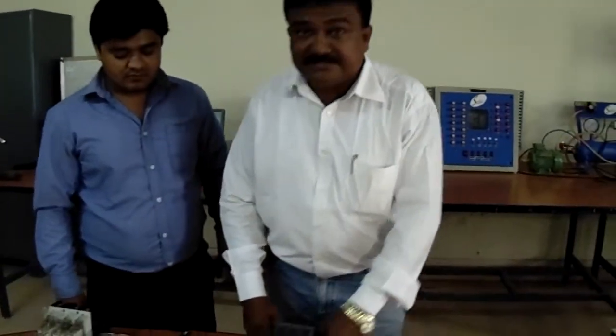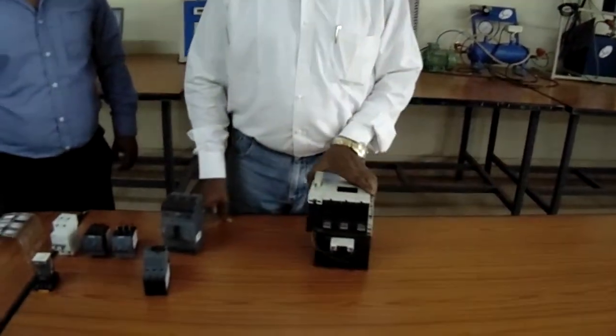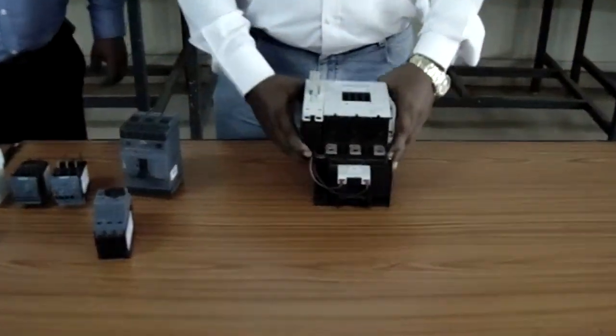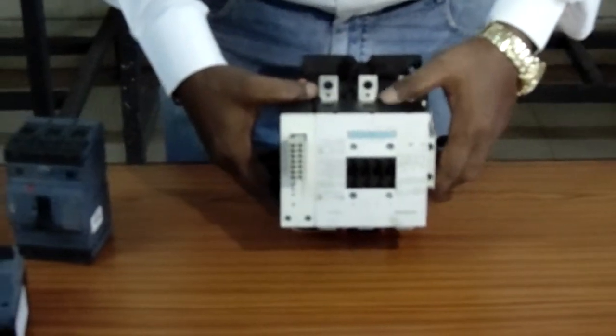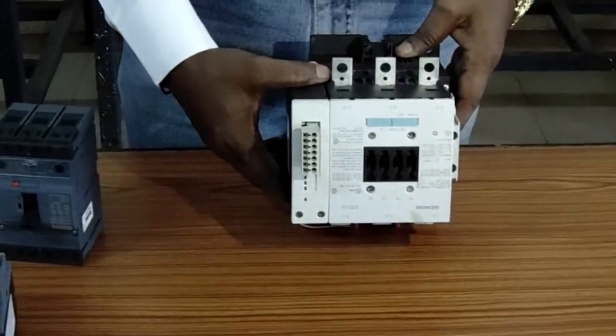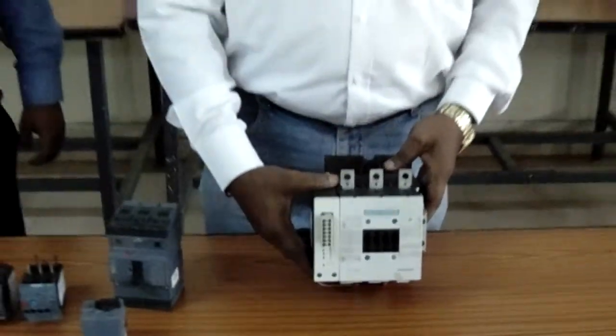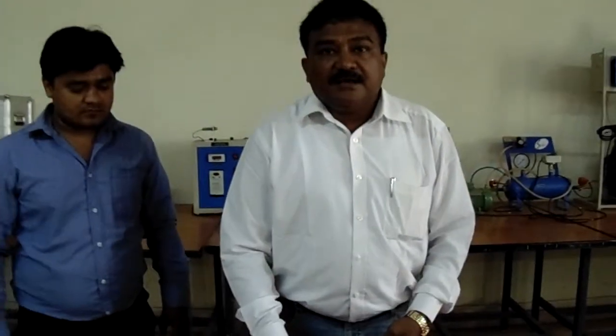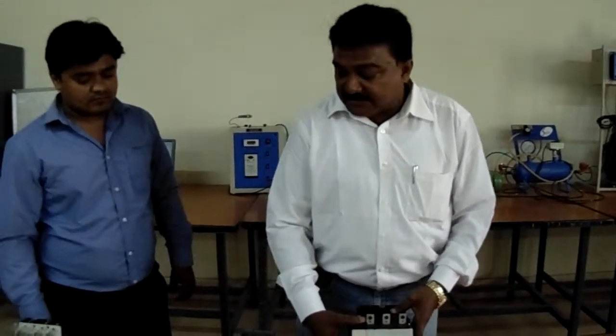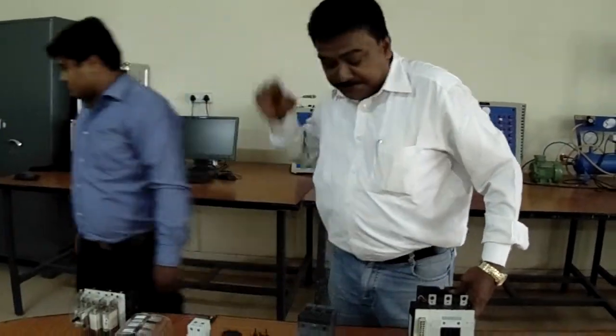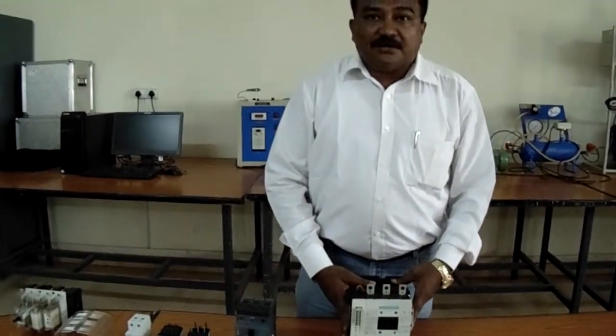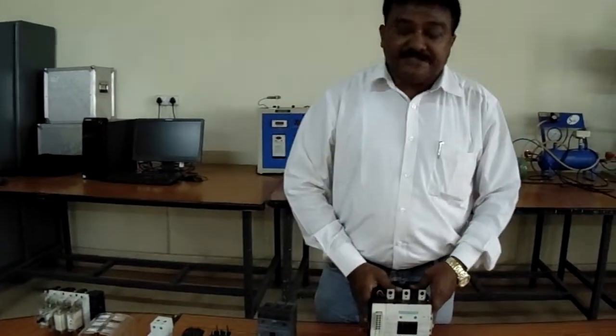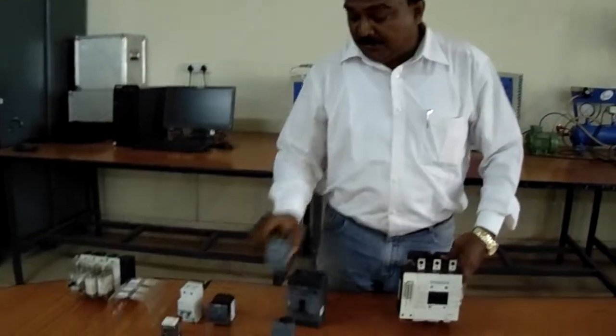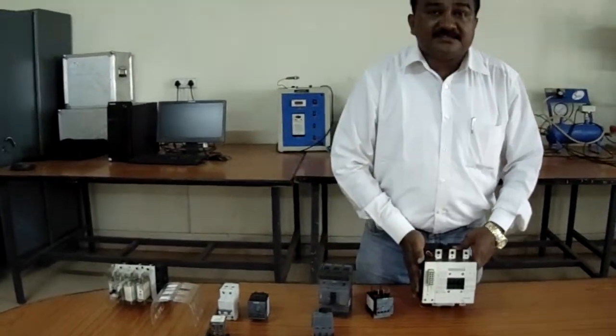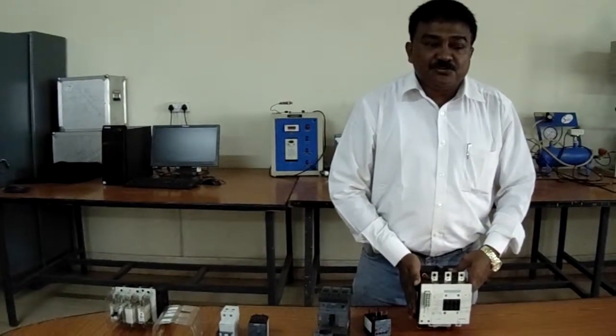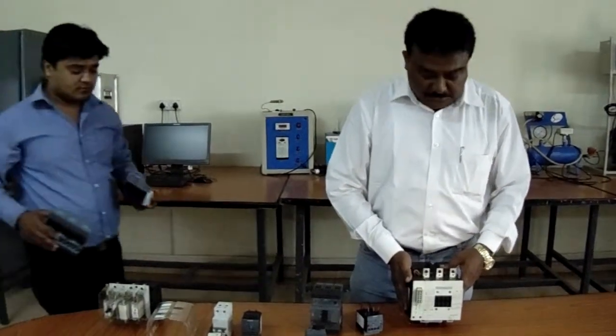Now coming to the starters of a 3-phase induction motor. Basically, conventional starters are divided into 3 categories: direct online starter, reversible direct online starter and star delta starter. After the isolators, the starter consists of the contactors and the overload relay. A contactor is a switching device which is used to start the motor.